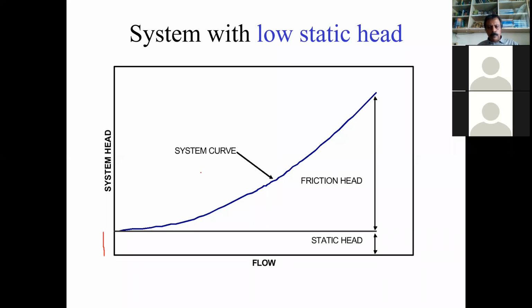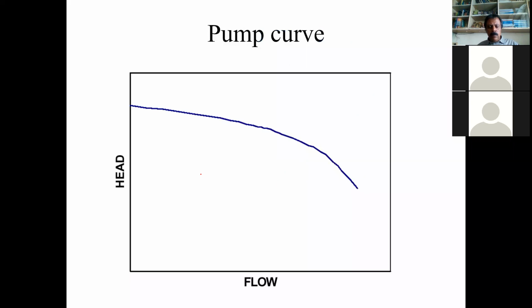So we have seen what the system curve is. Now going to the manufacturer. The manufacturer sells a pump. The pump has a curve which is called the pump characteristic curve. This is a pump curve. The pump curve is like this. As we have seen initially, the less the head, the more the flow. So as we keep on offering more resistance, head increases and flow decreases.